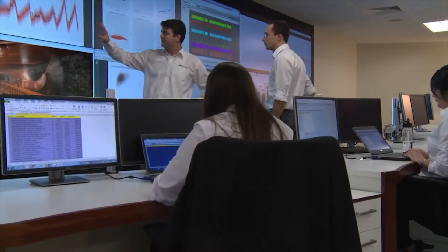The algorithms track normal behavior and flag issues with the conveyor. Within the first week of the Longwall starting up, I noticed excessive vibration on one of the gearboxes, detected by those algorithms. I called the local field service rep — part of our direct service component — to go to the mine, take a look at the gearbox with handheld vibration equipment, and confirm what I had seen on the computer. Through those recordings, we determined that corrective action could happen on the next scheduled maintenance period, meaning no unexpected downtime. Without this algorithm, it could have caused a transmission failure at a cost of about $2 million.